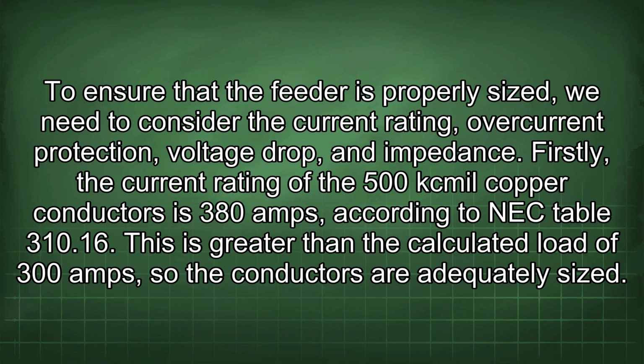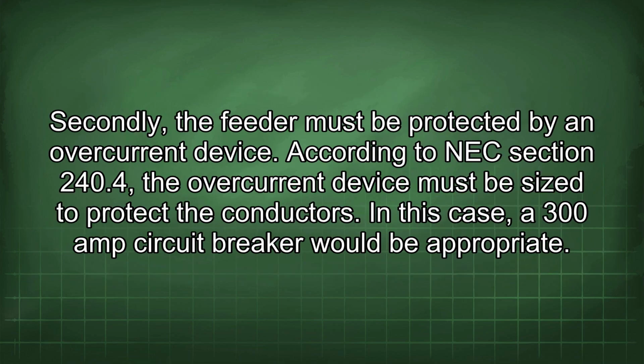impedance. Firstly, the current rating of the 500 kcmil copper conductors is 380 amps, according to NEC Table 310.16. This is greater than the calculated load of 300 amps, so the conductors are adequately sized. Secondly, the feeder must be protected by an overcurrent device. According to NEC Section 240.4, the overcurrent device must be sized to protect the conductors. In this case, a 300 amp circuit breaker would be appropriate.